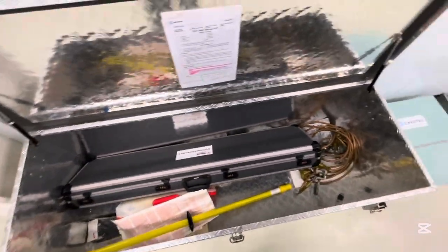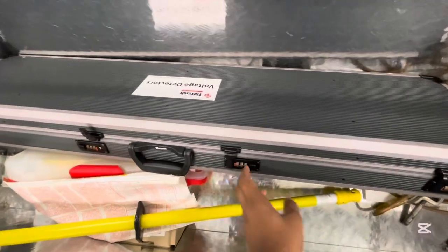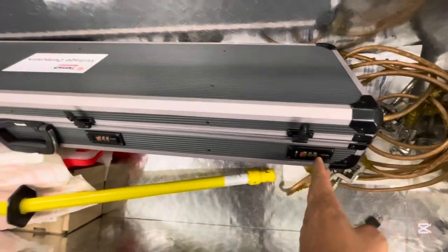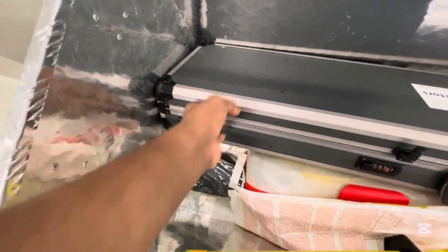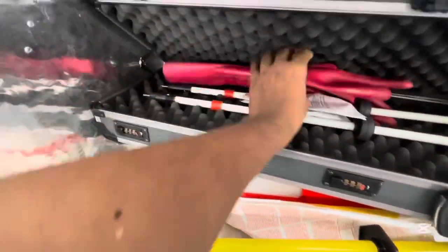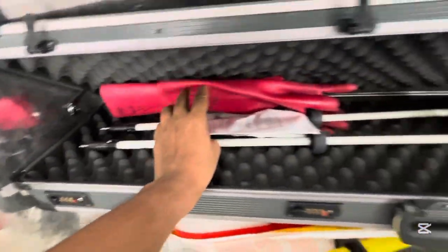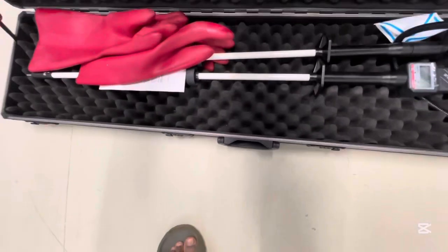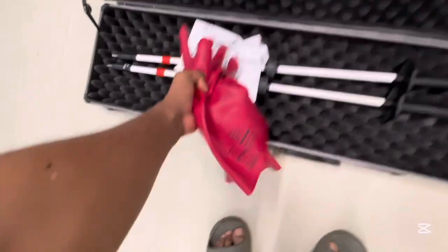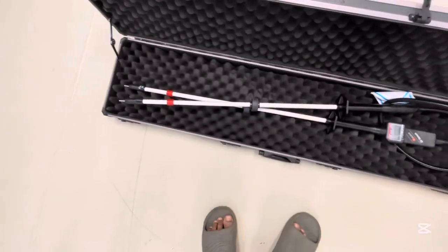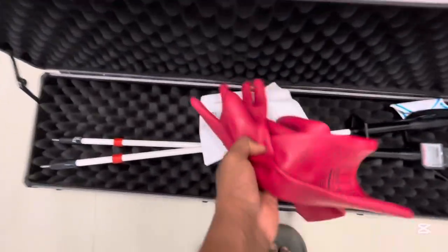Then we have something called a voltage tester. Once you disconnect the ACB and ground it in the main bus bar and switchboard, and also ground it from the machinery end, you have to confirm the machinery is totally grounded and ensure it doesn't have any static electricity or residual charges holding on to it. So you have to verify that using this stick.